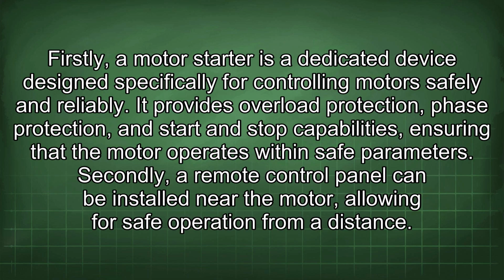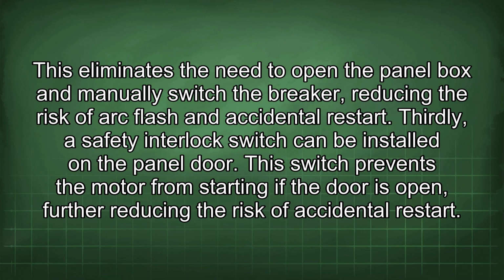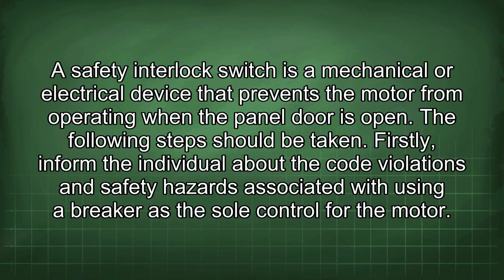Firstly, a motor starter is a dedicated device designed specifically for controlling motors safely and reliably. It provides overload protection, phase protection, and start and stop capabilities, ensuring that the motor operates within safe parameters. Secondly, a remote control panel can be installed near the motor, allowing for safe operation from a distance. This eliminates the need to open the panel box and manually switch the breaker, reducing the risk of arc flash and accidental restart. Thirdly, a safety interlock switch can be installed on the panel door. This switch prevents the motor from starting if the door is open, further reducing the risk of accidental restart. A safety interlock switch is a mechanical or electrical device that prevents the motor from operating when the panel door is open.